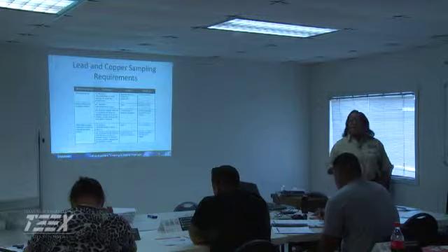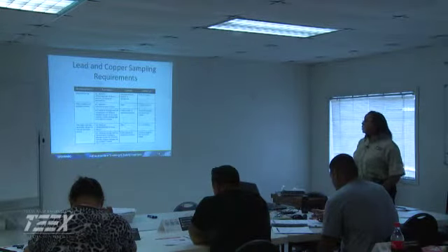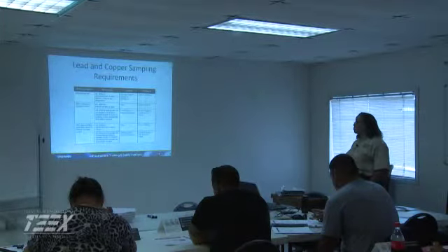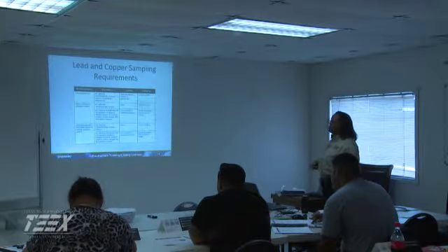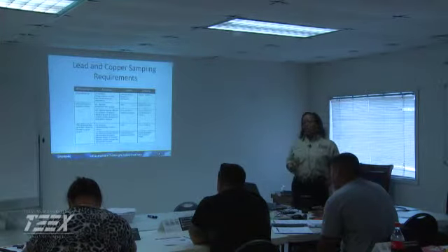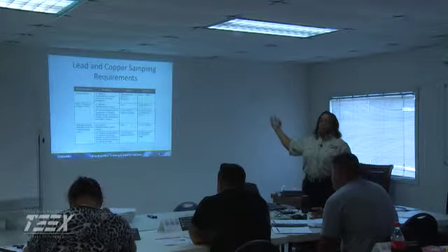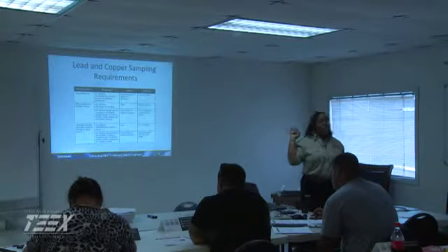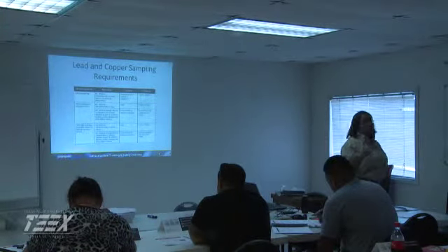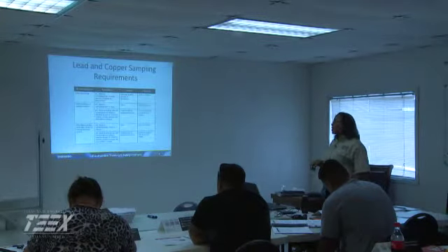That's when we've had a hit, when it's exceeded the 90th percentile. And it will be the same after your territory specifies optimum corrosion control. If they've specified that for that one system, you're doing those analyses at the same frequency: at the tap every 6 months, and at the entry of the distribution system every 2 weeks. Not less than every 2 weeks is what they say.